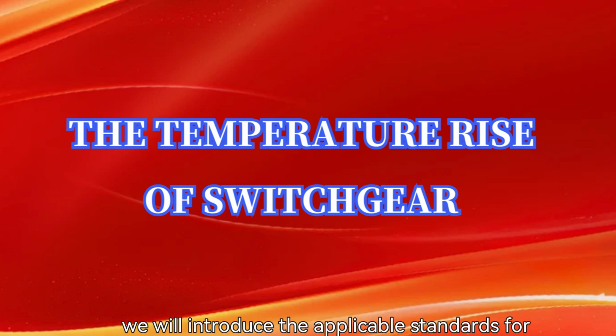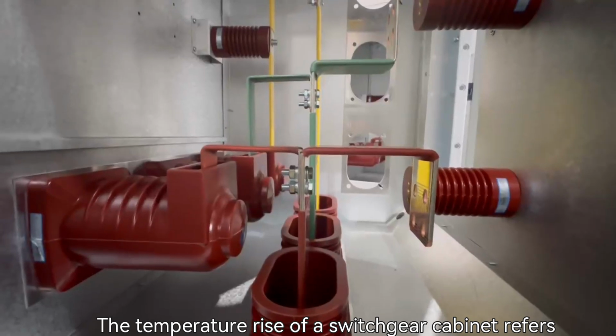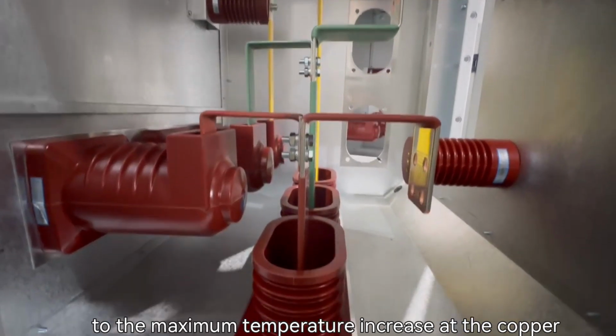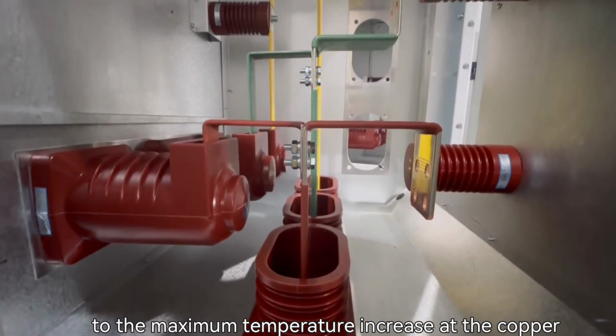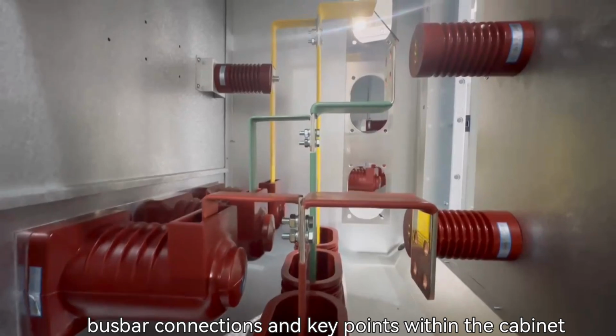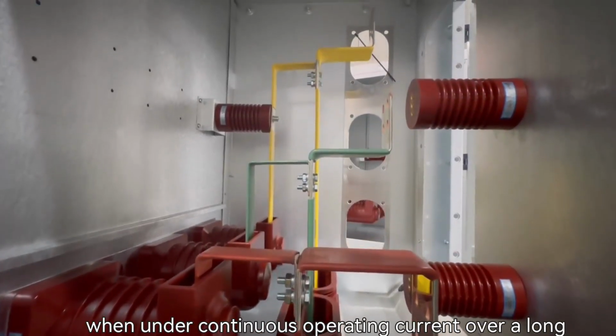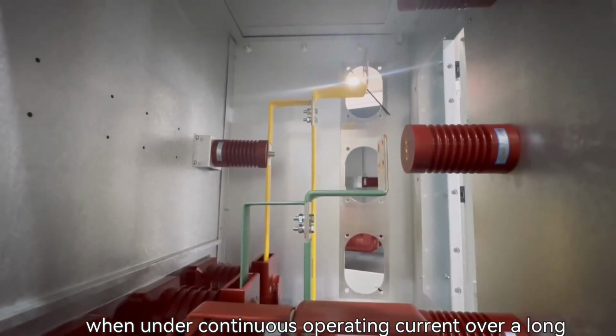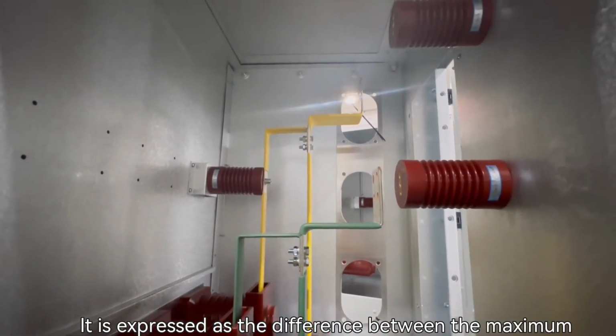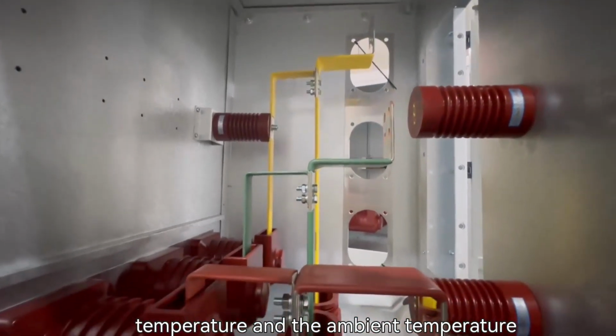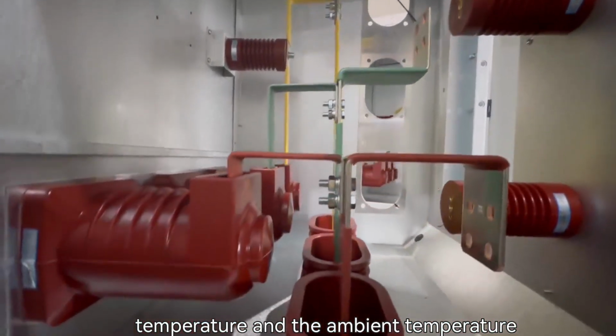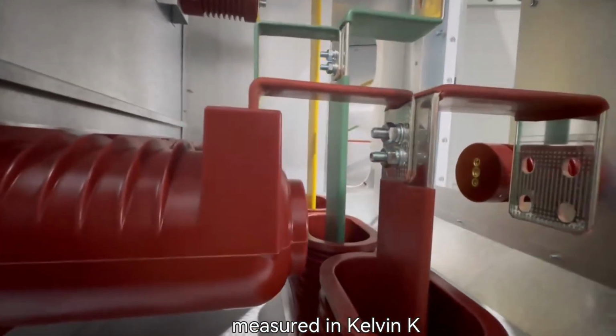In this video, we will introduce the applicable standards for temperature rise. The temperature rise of a switchgear cabinet refers to the maximum temperature increase at the copper busbar connections and key points within the cabinet when under continuous operating current over a long period of time. It is expressed as the difference between the maximum temperature and the ambient temperature, measured in Kelvin K.